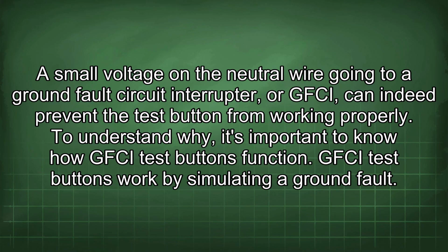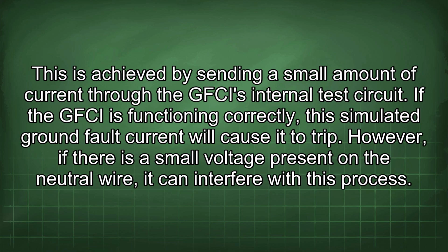A small voltage on the neutral wire going to a ground fault circuit interrupter, or GFCI, can indeed prevent the test button from working properly. To understand why, it's important to know how GFCI test buttons function. GFCI test buttons work by simulating a ground fault. This is achieved by sending a small amount of current through the GFCI's internal test circuit. If the GFCI is functioning correctly, this simulated ground fault current will cause it to trip.